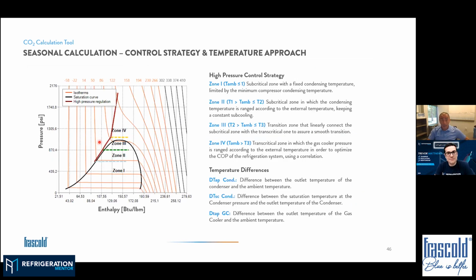On the high pressure side, as we said, there is a control strategy to be defined, and this is, how can I say, a big challenge, because it makes a lot of difference. So we do not have to forget that that system will not work transcritical all the time. Actually, in the Toronto example, we'll see later the number of hours in transcritical are pretty low. And so we have to define a control strategy, and you can decide.